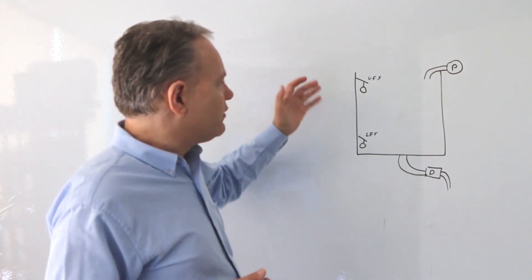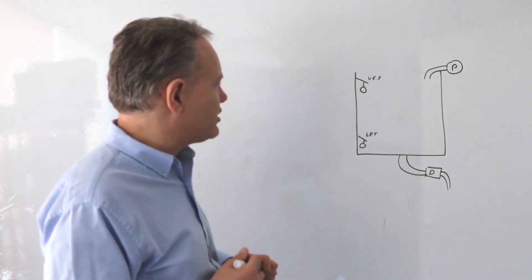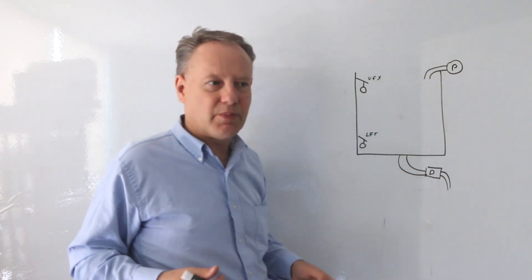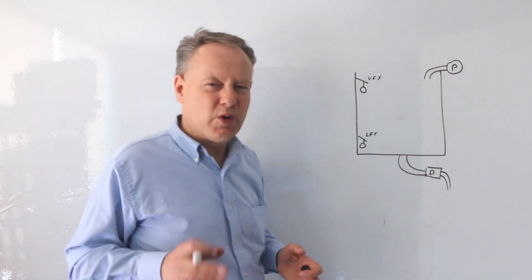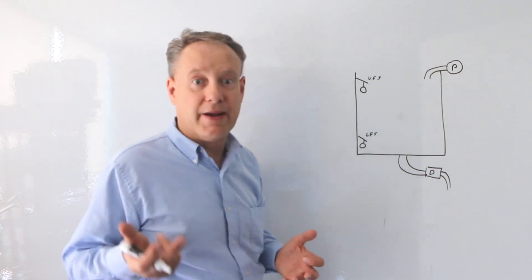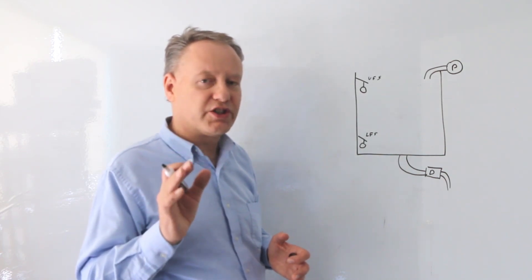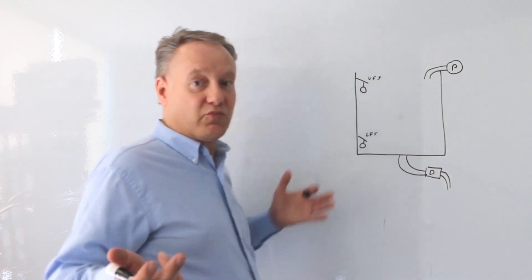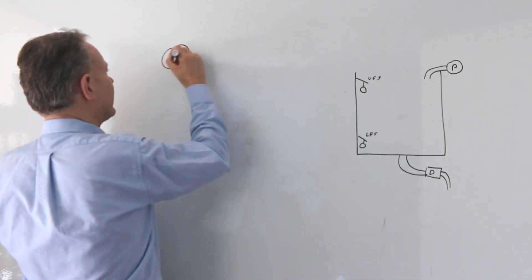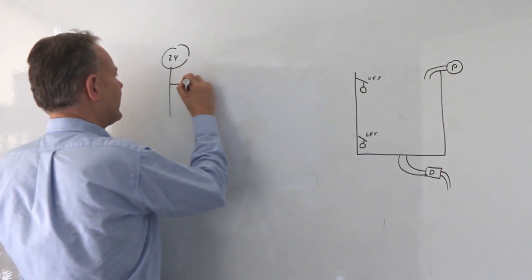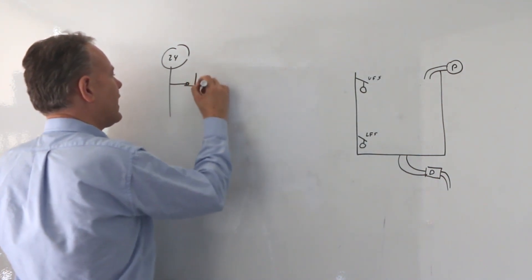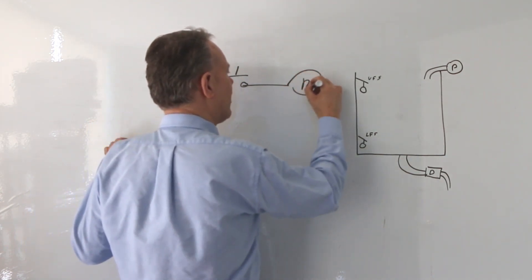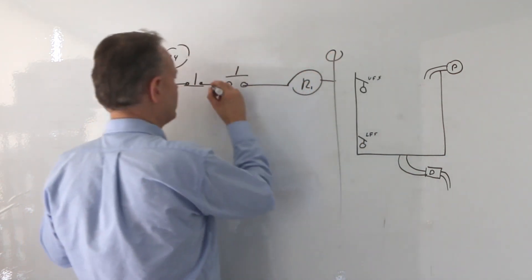We're going to put these into the application and look at when we want the pump to come on. We want the pump to come on when the tank gets empty, and we probably want to start the cycle with a button. So we're going to put a holding circuit in to start it with a standard stop/start rung. I'm going to draw 24 volts, put a stop in here and a start in here, and put my relay R1.